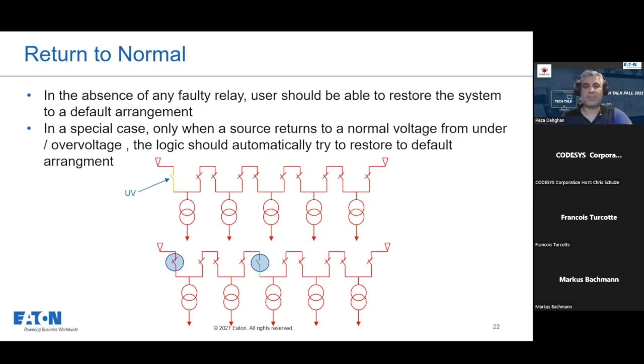Okay, yeah, the concept of return to normal. In the absence of any faulty relay, users should be able to restore the system to a default arrangement. There is one more, basically, that's just when the system is not faulty, but there is one special case, and it's when a source returns to a normal voltage from under or over voltage. This was a request specified by the protection and transformer team.